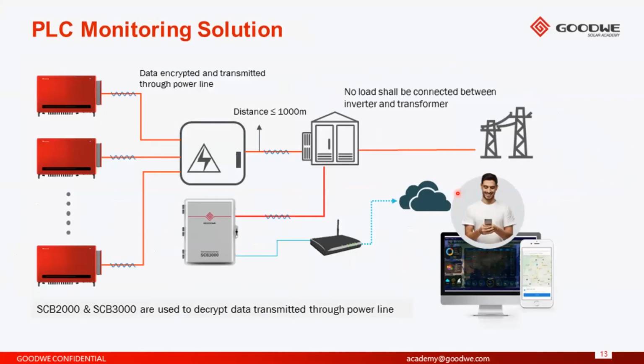In addition, we offer PLC monitoring solutions, which stands for power line communication. Rather than having a dedicated RS485 communication cable daisy chaining the inverters, in the PLC solution we're able to transfer the data from the inverter via the AC cable that is connected from the inverter to the distribution transformer or the step-up transformer. The advantage of this is that you don't have to install the RS485 cable, so you save on installation costs and cable costs.